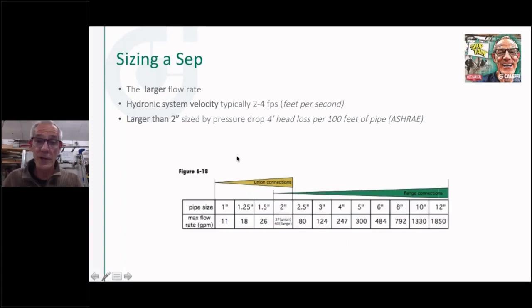You don't use this velocity, and that velocity tends to get sometimes bigger in the larger pipe. So if you're trying to size, say, a 4 or 5 or 6 inch pipe by this velocity number, you should really use this formula here. As I Googled around, I found there's different opinions on what this number should be. But again, this is the ASHRAE, and if you put your faith and trust in the engineers at ASHRAE, that's probably the safe number to use. I bet there's a little bit of wiggle room in that also, knowing the way that they come up with those formulas. So am I clear on the sizing of a hydraulic separator? The larger flow rate, whatever side, primary or secondary, it doesn't matter. The larger of the two is what you size the separator to.